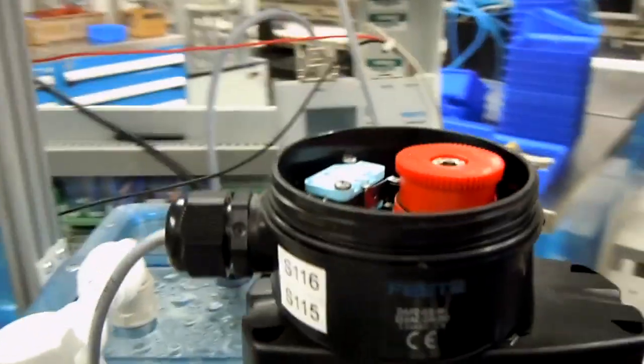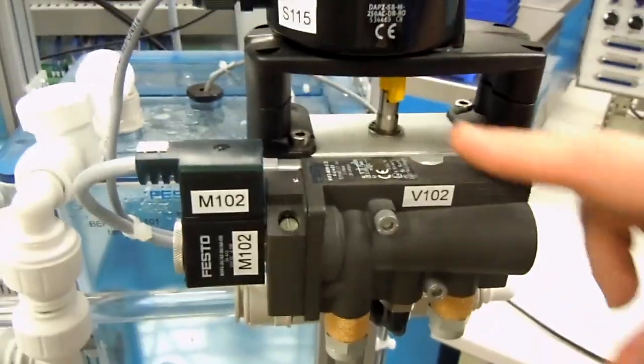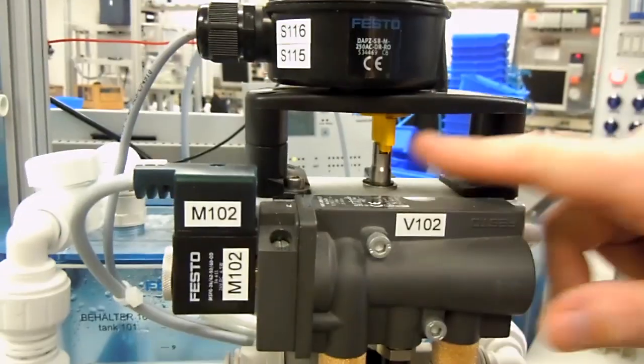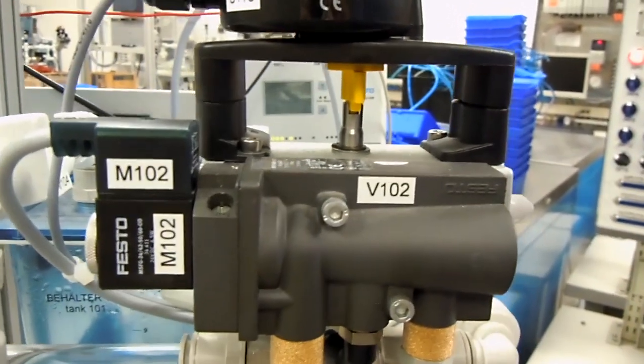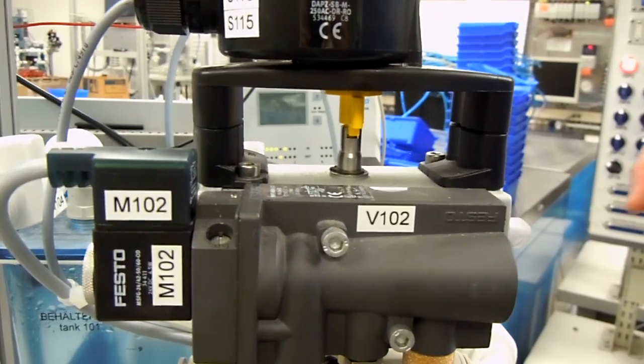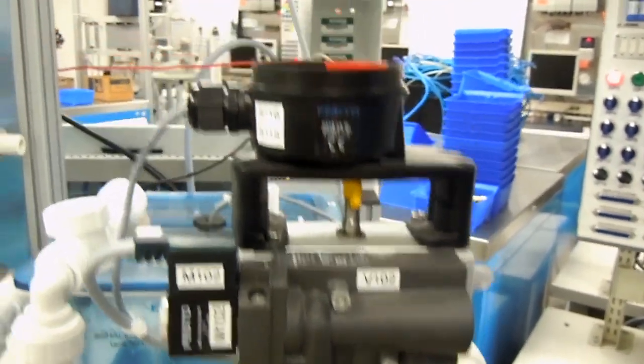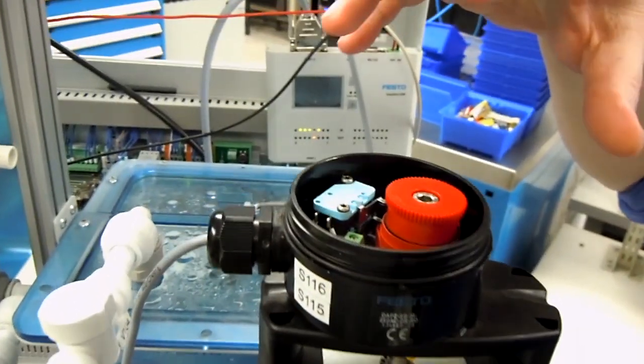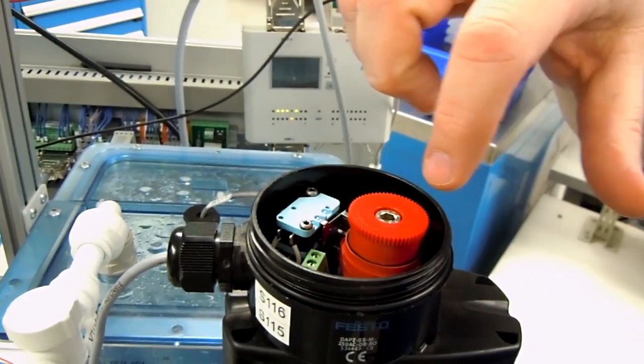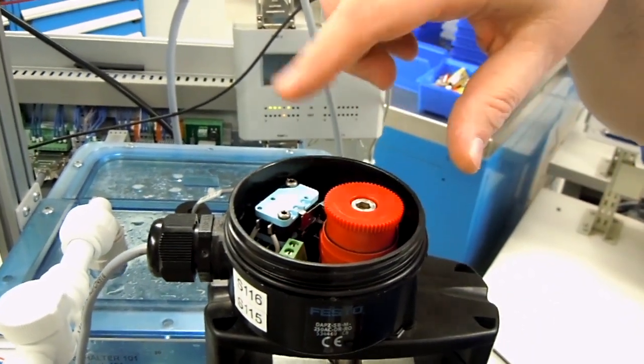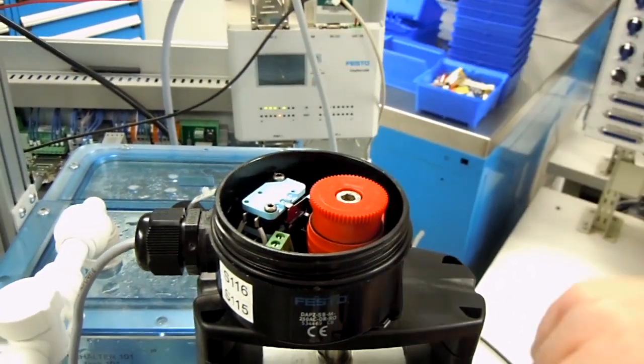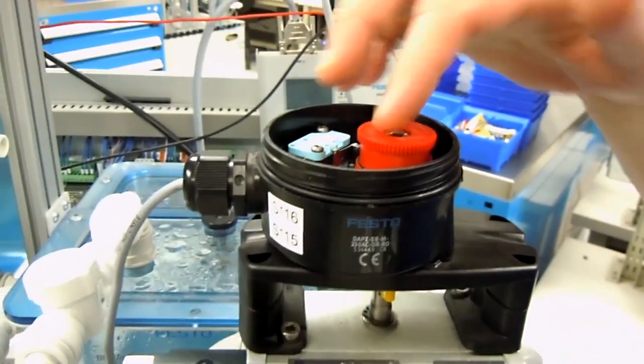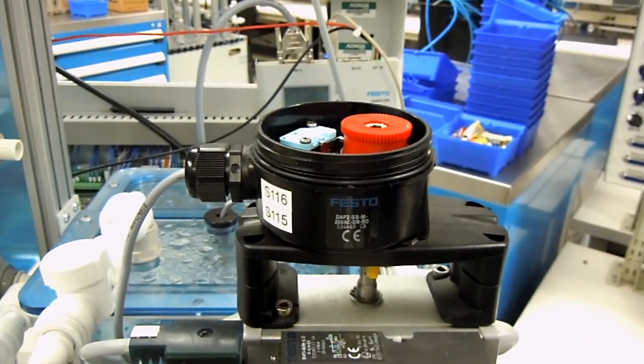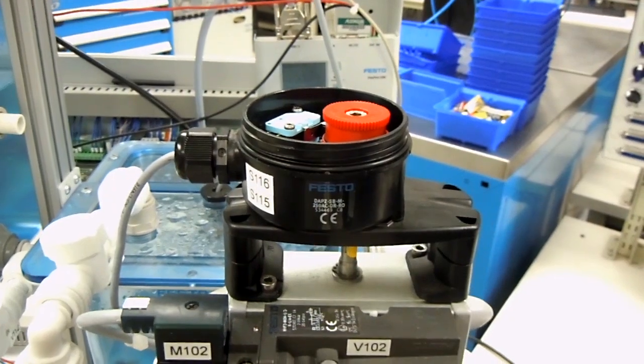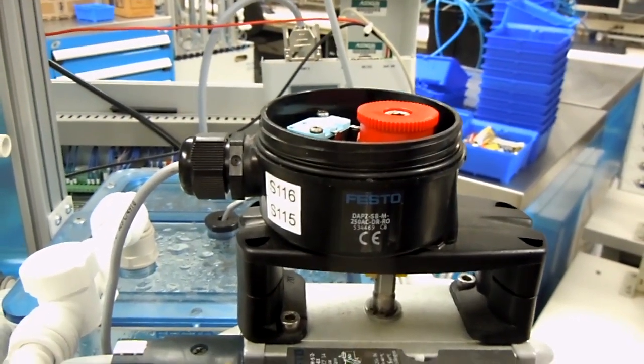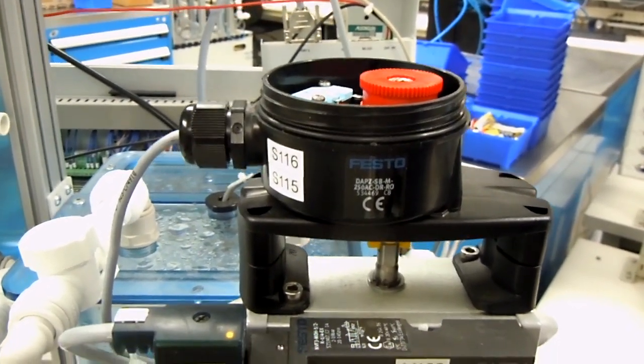So right now, I can tell that this valve is closed because this little yellow indicator is perpendicular to the tubing, so it's not allowing any flow through here. And up here is the ball valve, but this thing's actually going to turn 90 degrees clockwise, 90 degrees counterclockwise to control this and the feedback switches. So let me just try that. So I'm going to get it to open. Okay, and you saw that yellow indicator change.